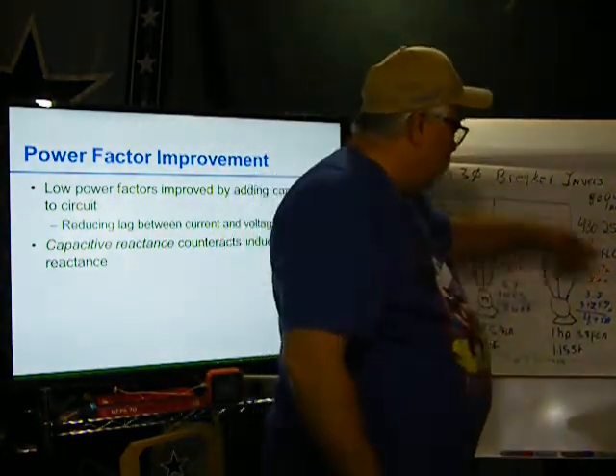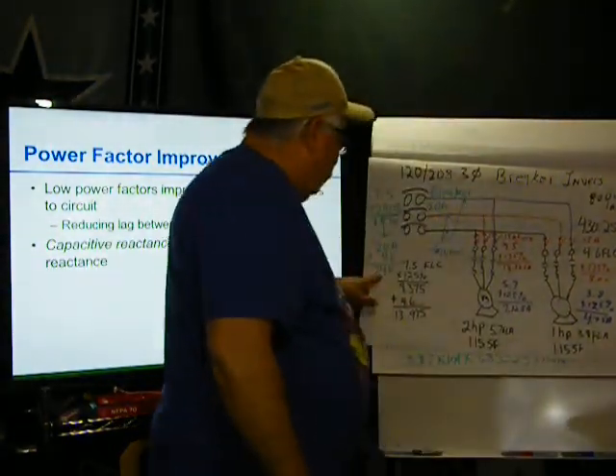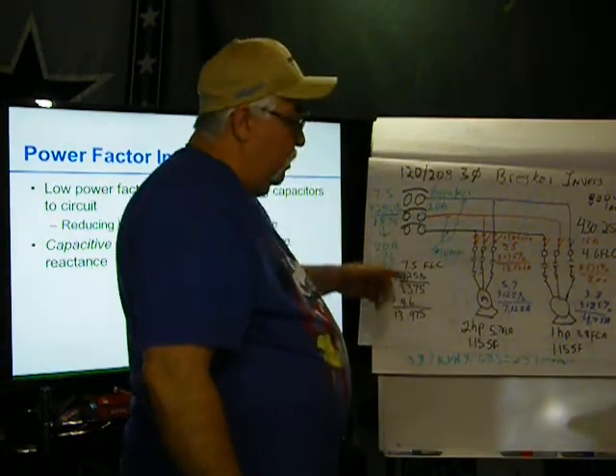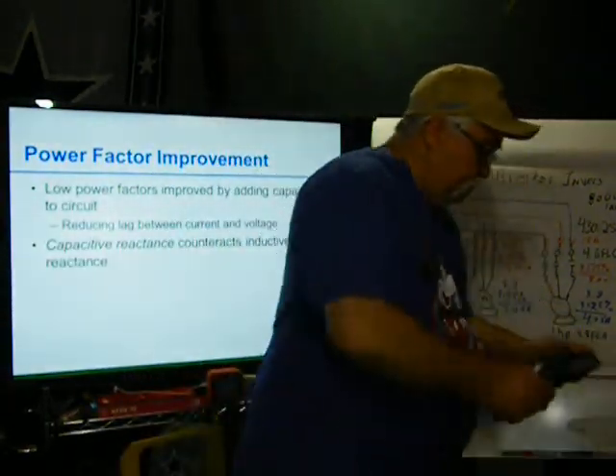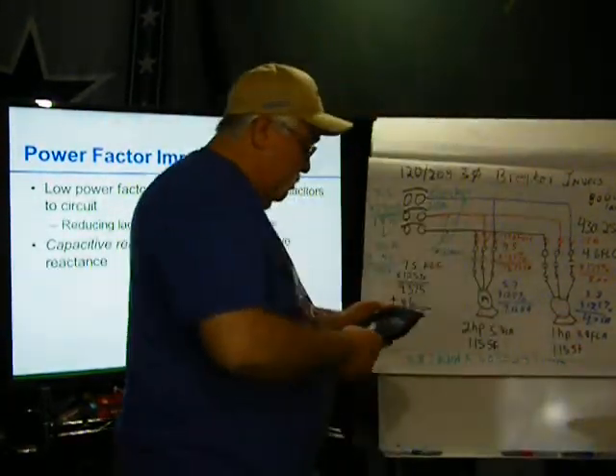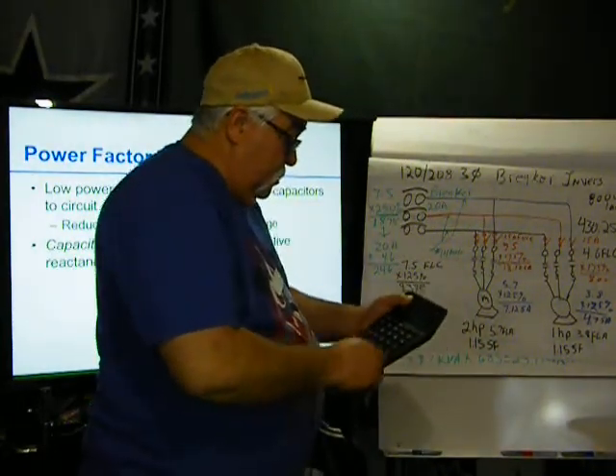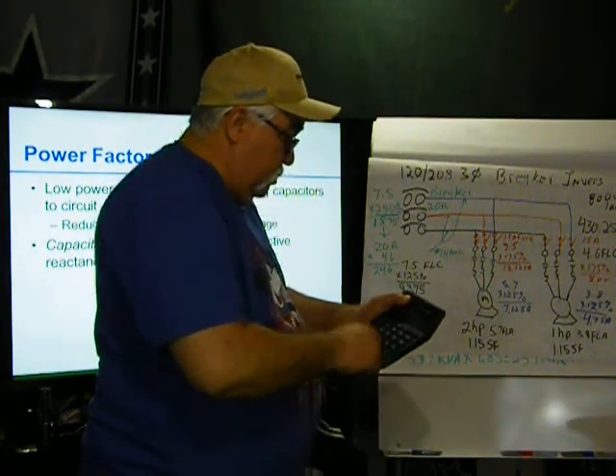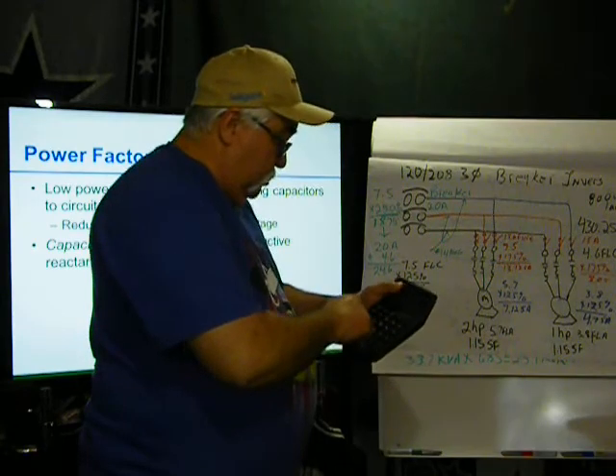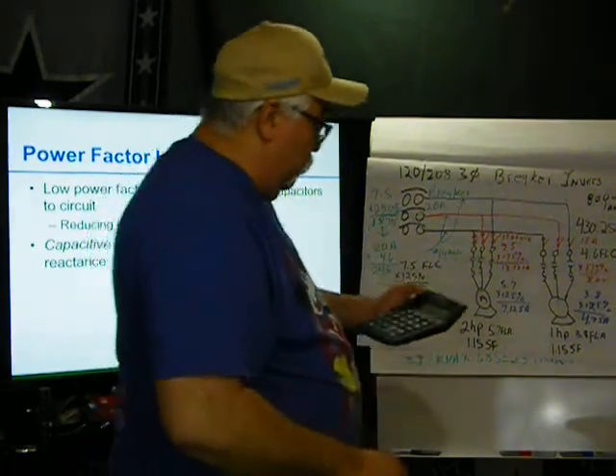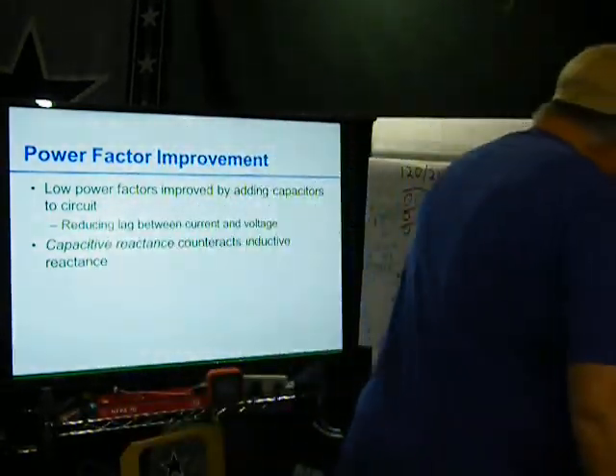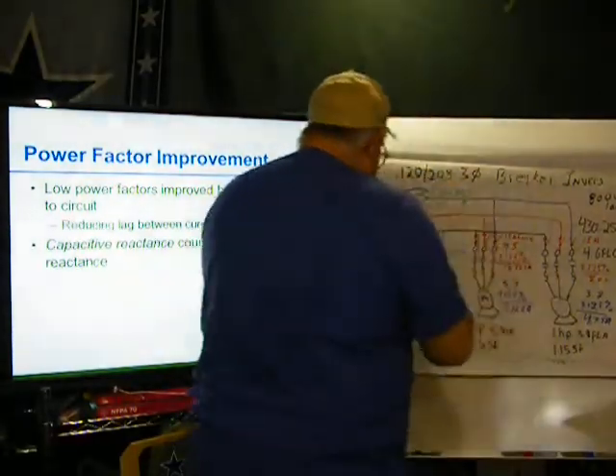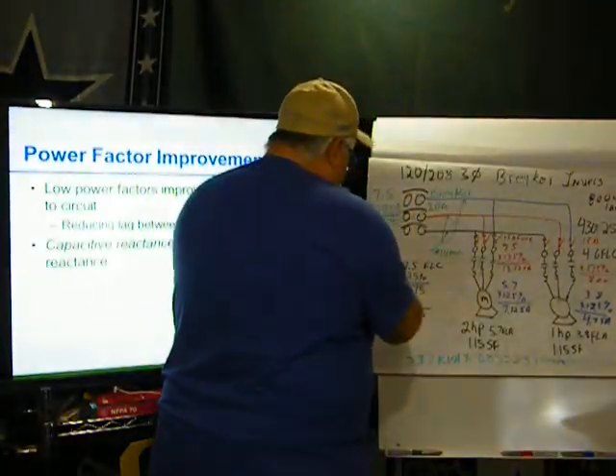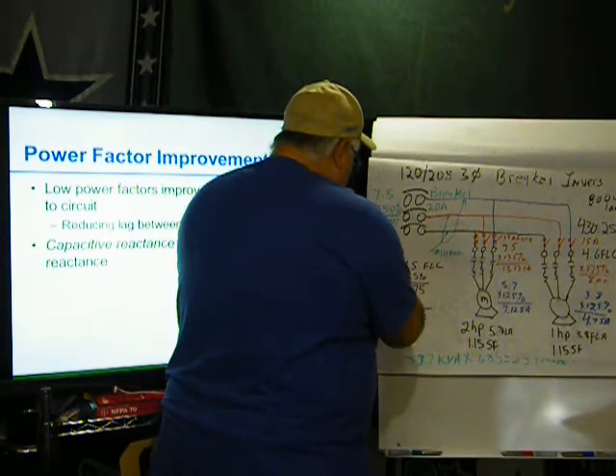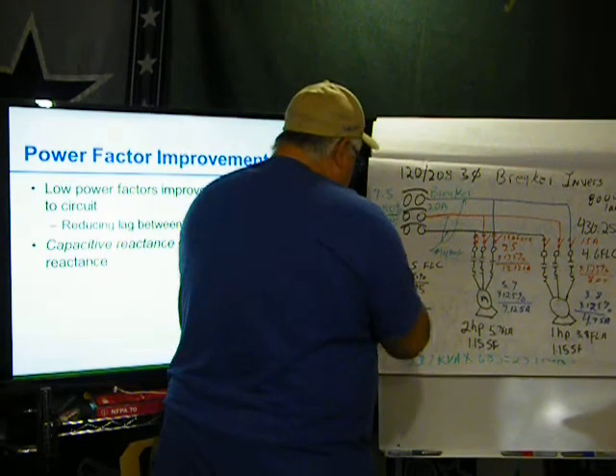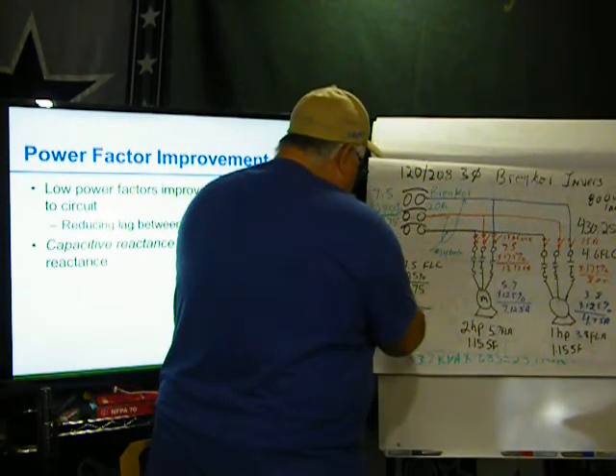Okay, this 800 watts, I would add it here. So if I get 800, let's say I'm adding an 800 watt load. 800 divided by 208 divided by 1.732 equals 2.2 amps. Okay, so I will add it here. 2.22.